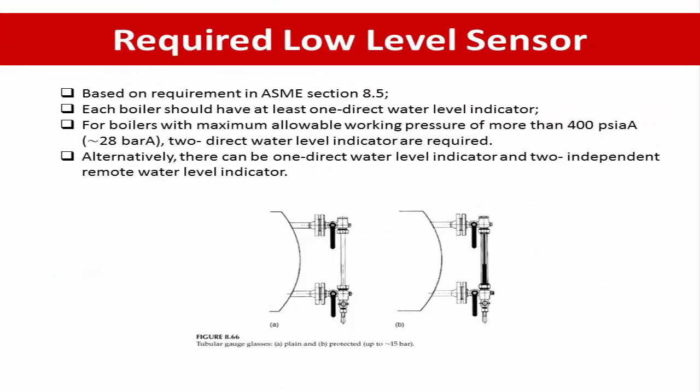Water level indication or gauge glass should be installed in a boiler drum, either for direct or remote viewing. As per ASME Section 8.5, the required number of water level indicators are: each boiler should have at least one direct water level indicator. For a boiler with a maximum allowable working pressure of more than 400 psi, approximately 28 bar, two direct water level indicators are required. Alternatively, one direct water level indicator and two independent remote water level indicators may be used.